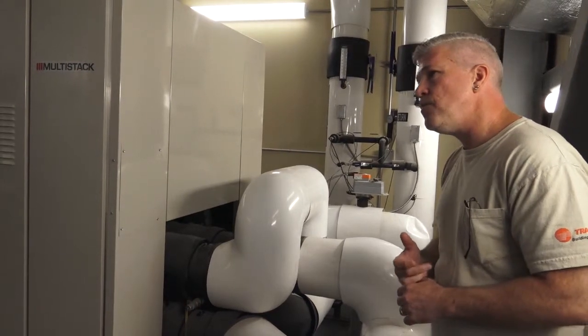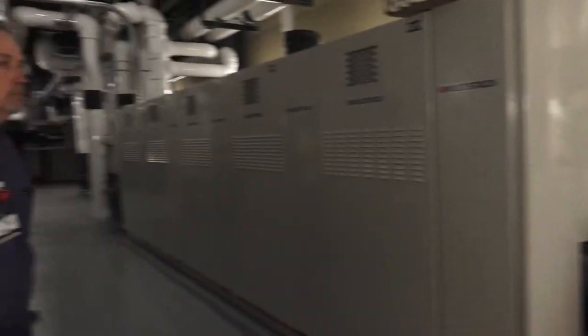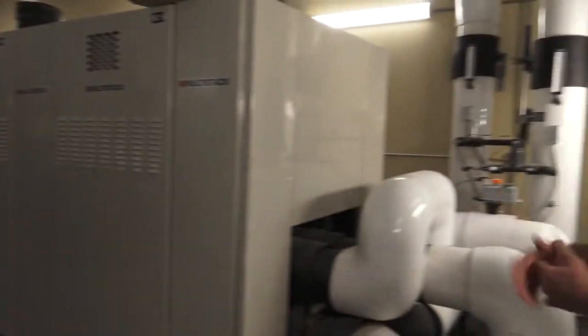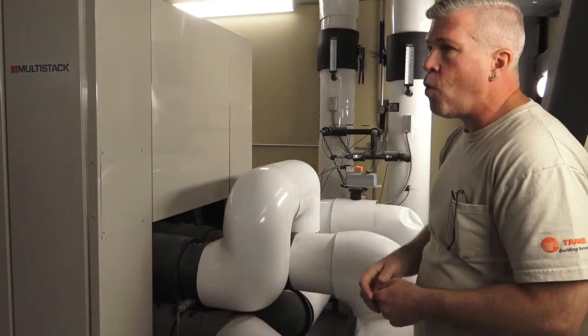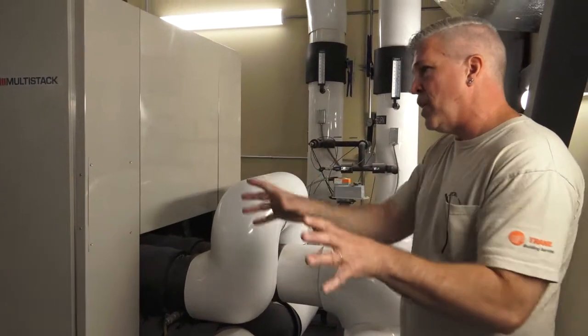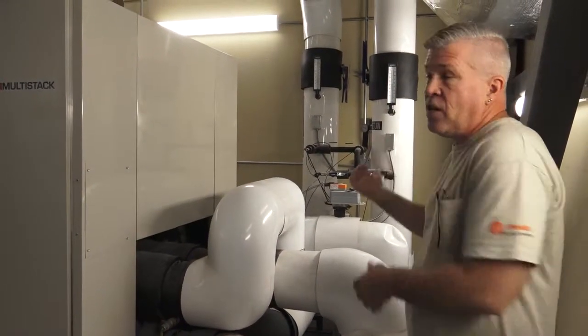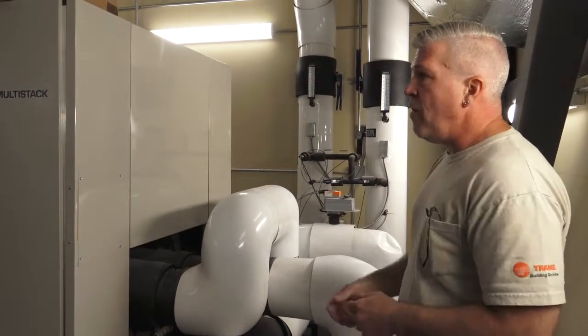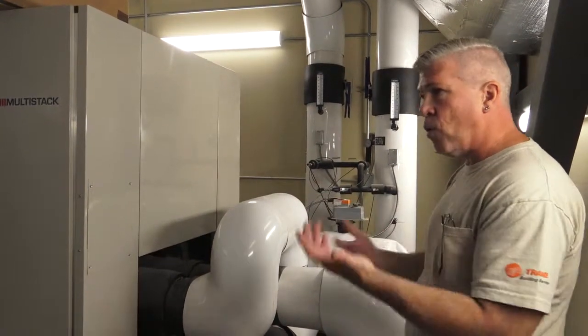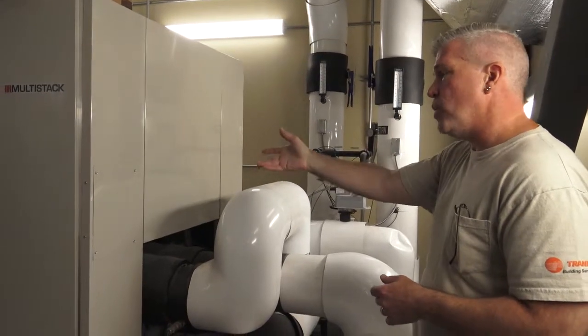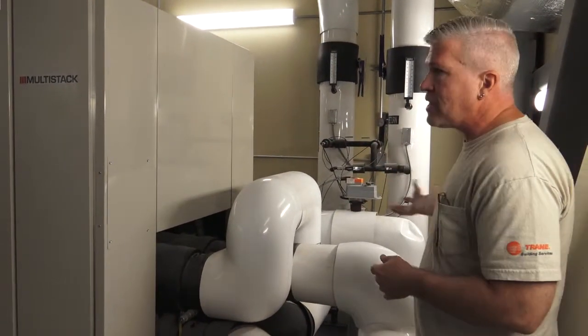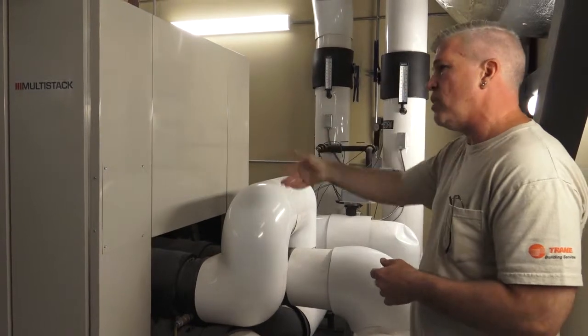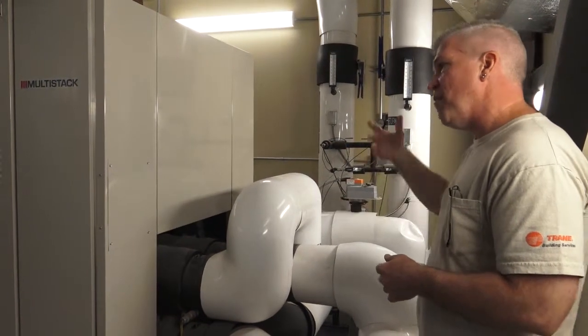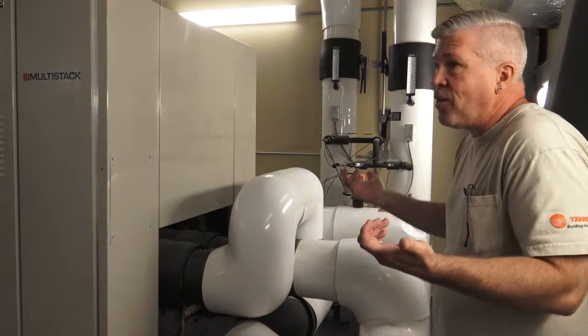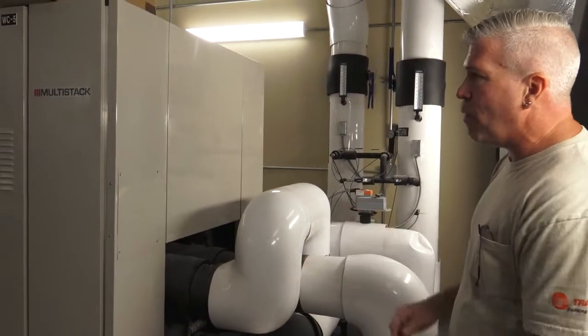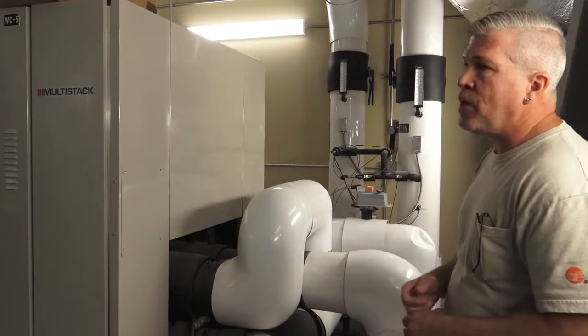So in the summer the field gets warmer, in the winter it gets cooler. During the summer, when you're cooling the building and producing chilled water, the excessive hot water the building doesn't need just gets dumped to the field, and it could be 120 degrees for all you know. Then when winter rolls around and you're producing a lot of hot water, it pulls back some of that warm water from the field, which helps it run. But you might see that field water coming back at like 45 degrees. It's weird the way it works, but that's what it's supposed to be doing.